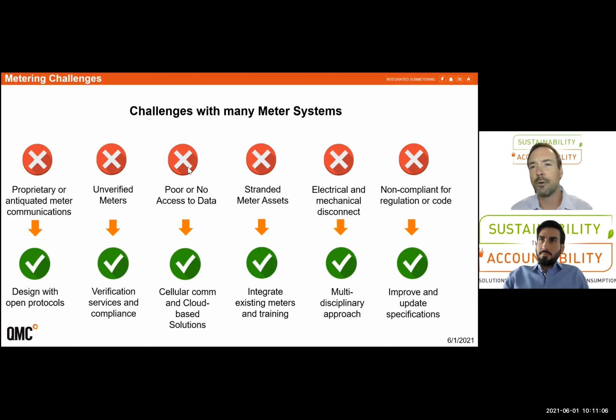Poor data or no access to data. We've seen lots of meter systems deployed where the people who need the data cannot get it. One of our first LEED M&V projects we did in about 2010, we were dealing with a lead consultant who said they've deployed 10 systems and still haven't seen any meter data from them. And one of the challenges was they were continually relying on the building automation system to collect that meter data. And it's often a low priority to get that as opposed to setting up the HVAC systems and other things on the control system.